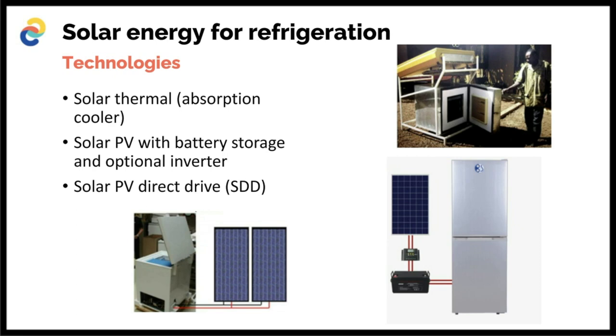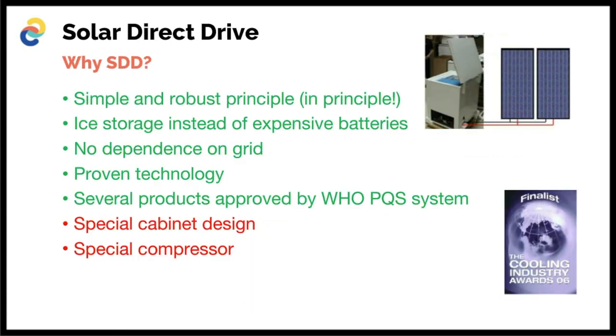So how does it work? In principle, it's very simple. You just connect the DC solar panels to a DC compressor, and then it will run. It's not that simple though, because a compressor needs a certain inrush current. So if you do nothing else, you need to oversize the PV panels to a very high safety factor of 4 to 5. This is not an economical way to do it.